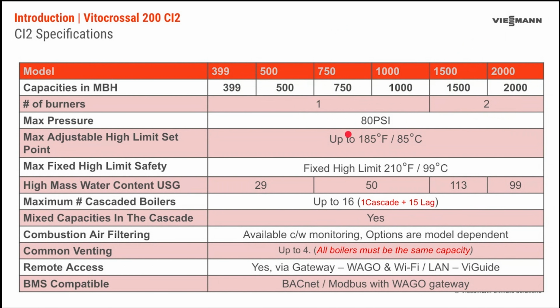Maximum pressure is 80 psi. We will actually supply the boiler with an 80 psi relief valve. It can be ordered with 30, 45, or 60. Adjustable high limit, 185 degrees Fahrenheit, with a fixed high limit or a trip limit of 210.